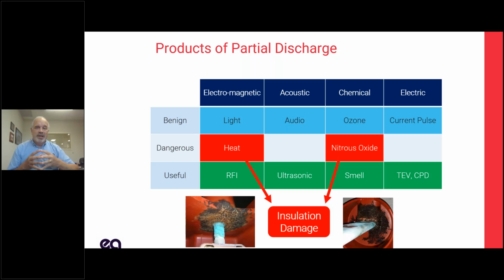There are a number of chemical effects that happen with surface discharge and with corona, but it doesn't happen with internal discharge because it's contained, you're not exposed to air. So when you have this spark in air, you have a breakdown of the air molecules that are ionized.